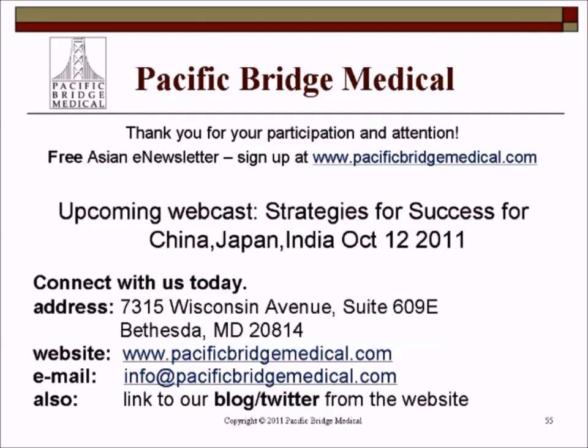What's given is that you definitely need the manufacturer's license - that's key. If you're not supplying into Singapore, you don't have to register with HSA itself. The manufacturer's license gives you permission to manufacture as well as supply, meaning export out of Singapore. But any time you choose to use it in Singapore, you then need the license. If you're not supplying in Singapore, you don't have to have the product registration done.